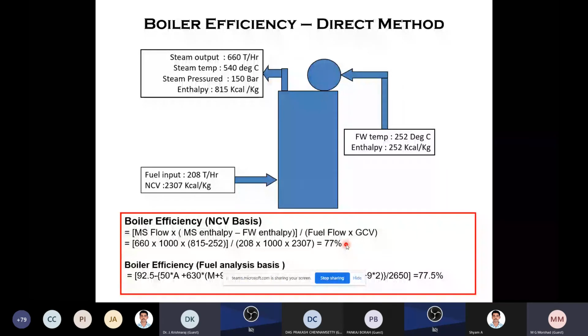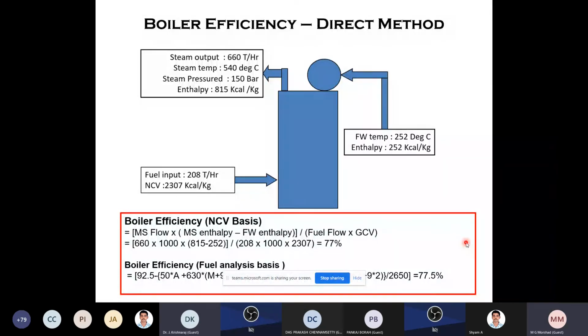But we do not know where the remaining 23% is going. We know 77% is the efficiency, but where is the other loss? This 23% loss is there, in which form is it going? That we do not know. So for knowing this portion, you have to go for the indirect method. Indirect is somewhat typical, and mechanical people who have studied thermodynamics will know how the boiler efficiency is calculated in the indirect method.